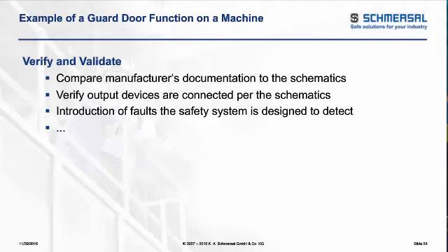We really need to compare all those devices by looking at the manufacturer's installation instructions, comparing it to the schematics to make sure the schematics were drawn up per the manufacturer's installation instructions, or the designs have been implemented outside of the unit, such as breaking the main power per proper safety levels.